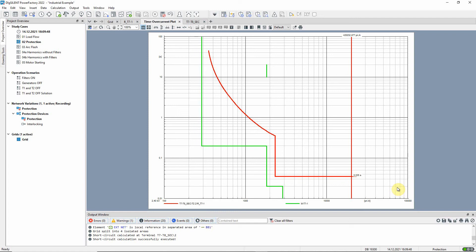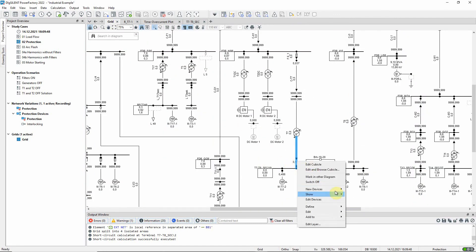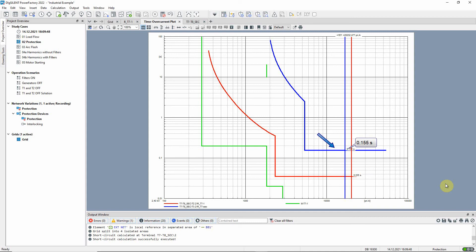Let us check the selectivity of this relay with the one above by adding that relay to the same time over current plot. For the same three phase short circuit, the primary relay shown in red will trip in 0.035 seconds and the one above shown in blue in 0.155 seconds. This means that the blue one will act as a backup if the red one fails to trip.